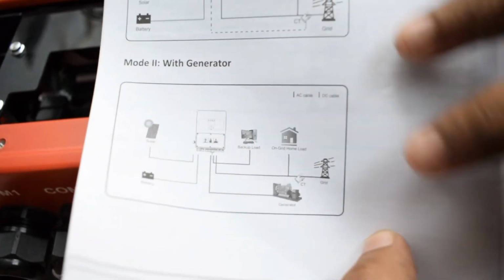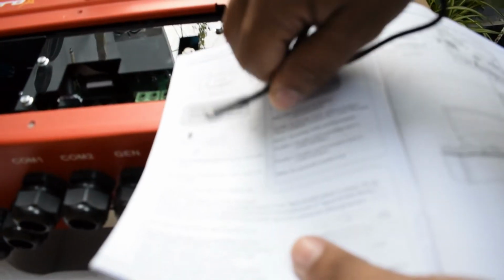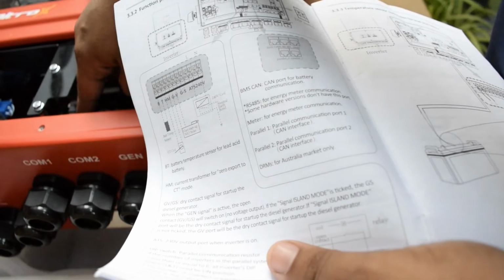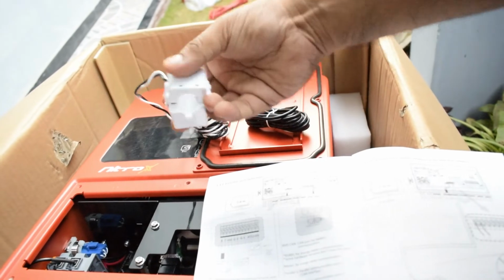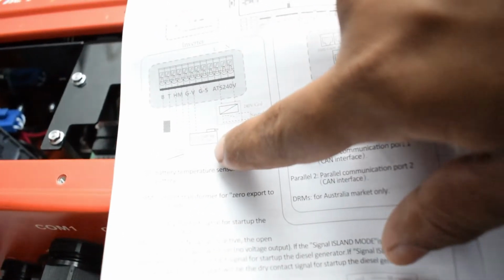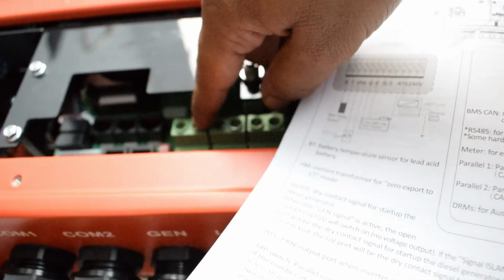With the second mode we have a generator. So we connect the generator, and now we have the function of the generator port, the function port. The function port's first 2 points are for the temperature sensor. This is the temperature sensor, that needs to connect with the batteries for their safety. The second, third and fourth ports of this function port will be utilized for the CT transformer for measuring the grid amperes, and the 5th and 6th ports are for the relay switch of the ATS, generator ATS. Yes, for the generator, and the last 2 ports will be utilized for generator line and neutral.